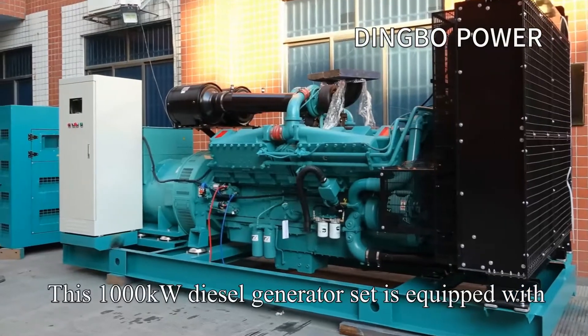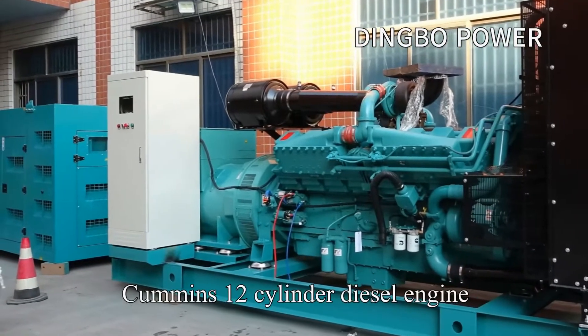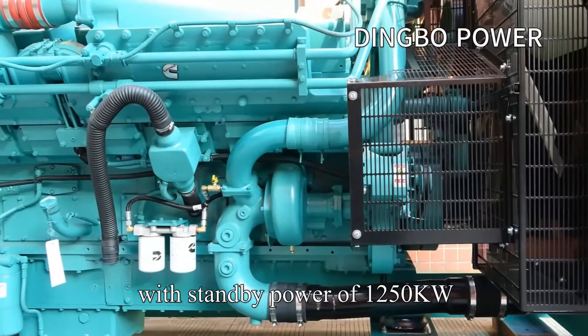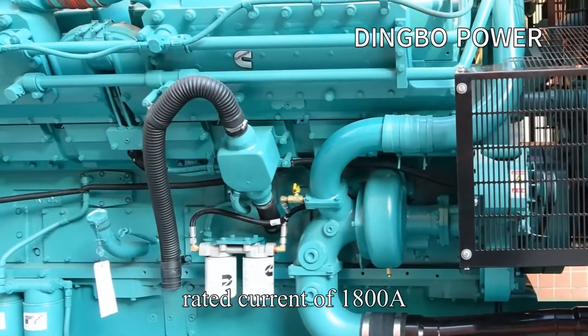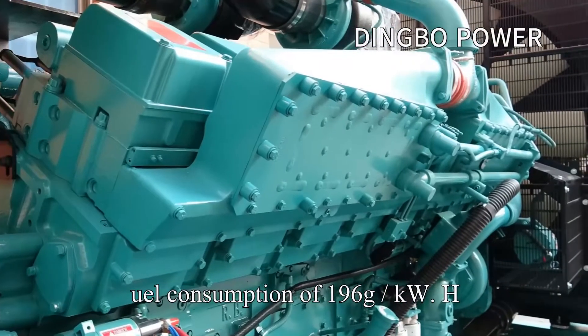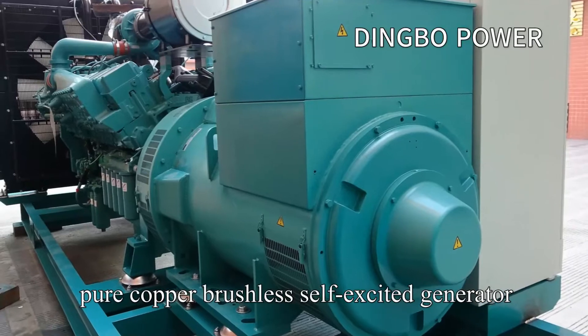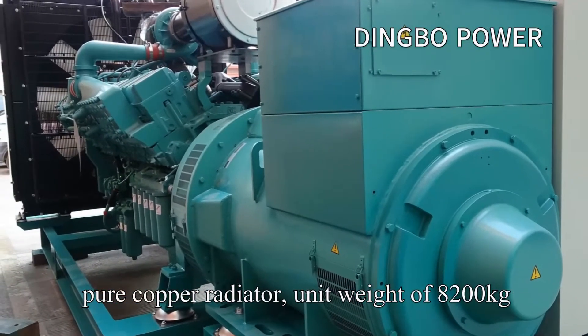This 1,000 kW diesel generator set is equipped with a Cummins 12-cylinder diesel engine, with standby power of 1,250 kW, rated current of 1,800 ampere, fuel consumption of 196 g/kWh, displacement of 37.8 liters, pure copper brushless self-excited generator, and pure copper radiator.